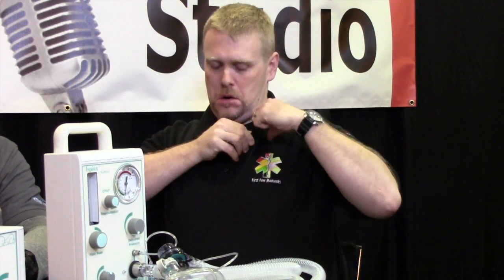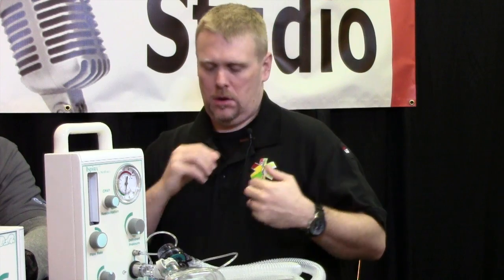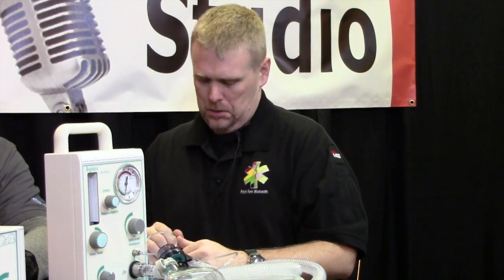Now, I like to feel compliance. I had that bag valve in my hand, and I like to be able to feel the compliance, but you can't with the positive pressure. Well, that's true. That's one concern people have. But there have been a number of studies at hospitals like Johns Hopkins which show that if you totally occlude a bag valve and mask system, so that there is essentially 100% compliance, then you actually can't feel that versus an open circuit. The human hand isn't sensitive enough to detect these very small changes in pressure. We're only talking 18 centimeters of water here, and it's impossible even for trained people to really feel those differences. So it's going to be much more accurate in terms of volume delivery.